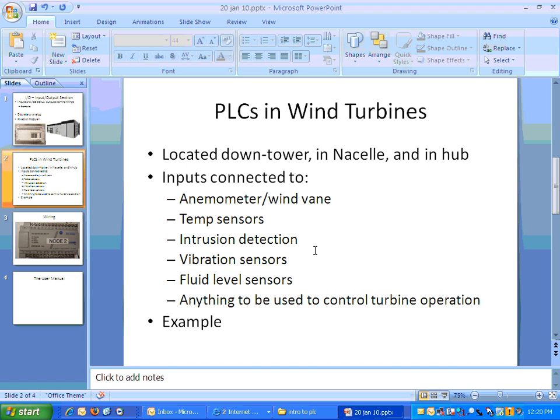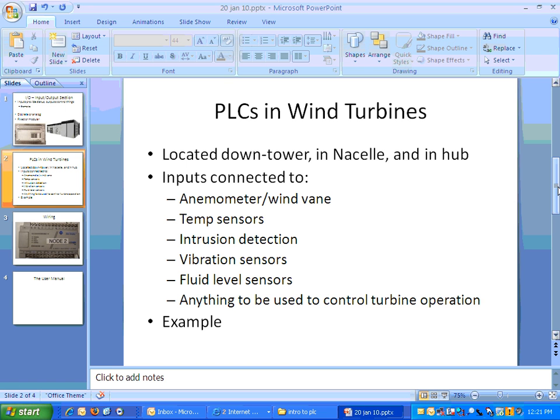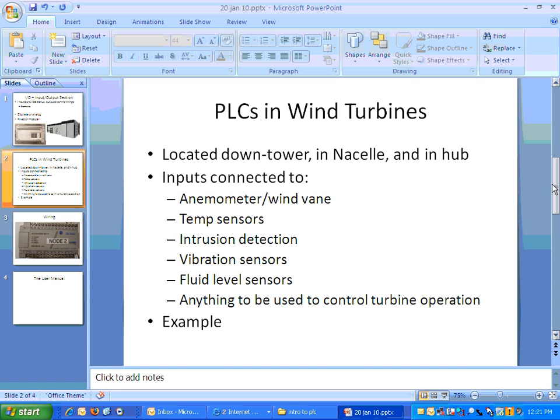Intrusion detection, if somebody opens a door, opens a cabinet, the PLC has that information. Vibration sensors, using the transmission again as an example, if a tooth on a gear gets damaged in some way and it causes excessive vibration when it operates, you need something to shut down the turbine and alert the maintenance personnel. Fluid level, for obvious reasons, you have to know if your fluid levels are getting low. Anything that can provide information to operate the turbine will have a sensor tied into the PLC. So, that information can be gathered and used to operate the turbine.